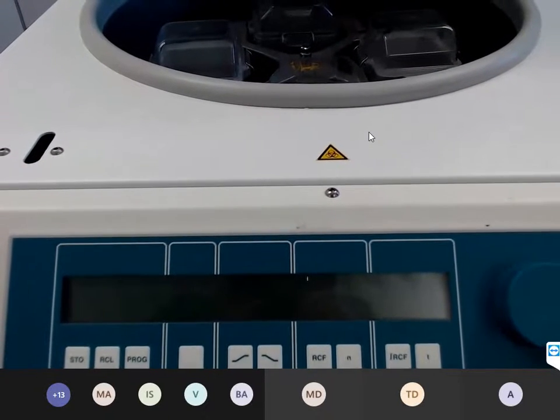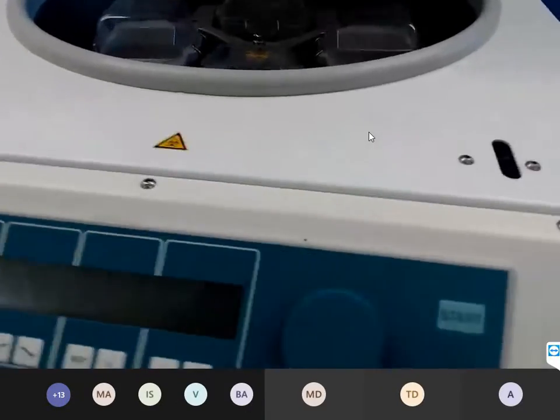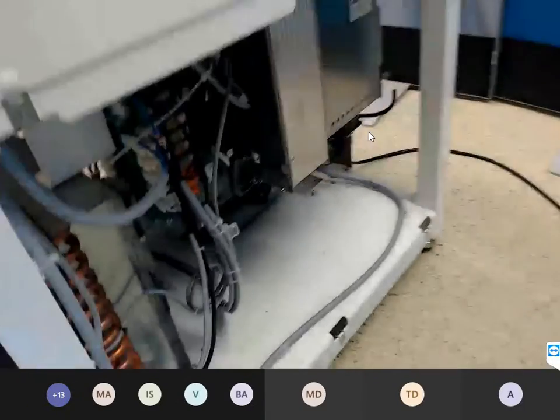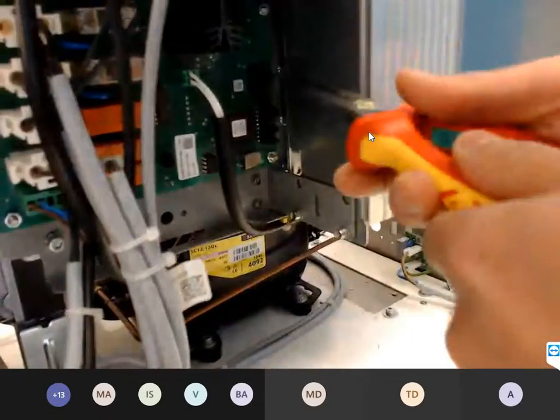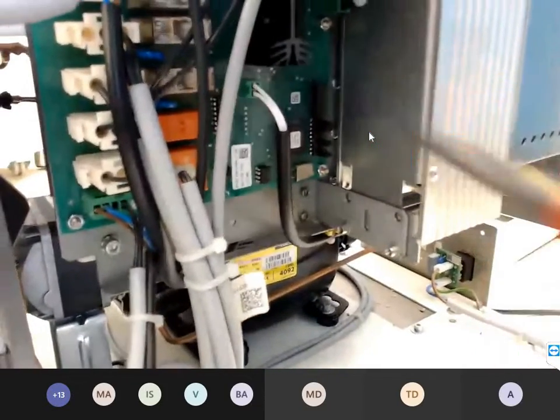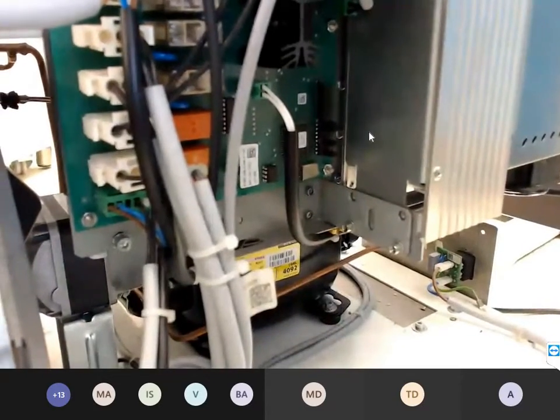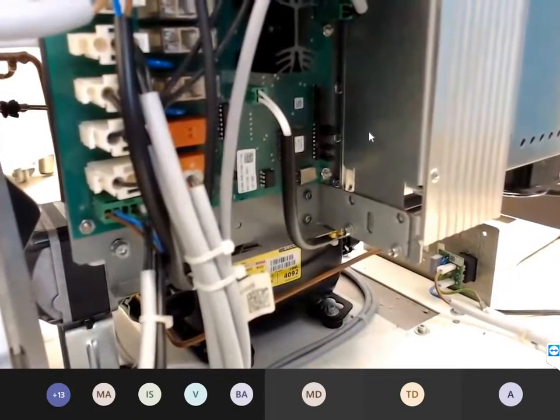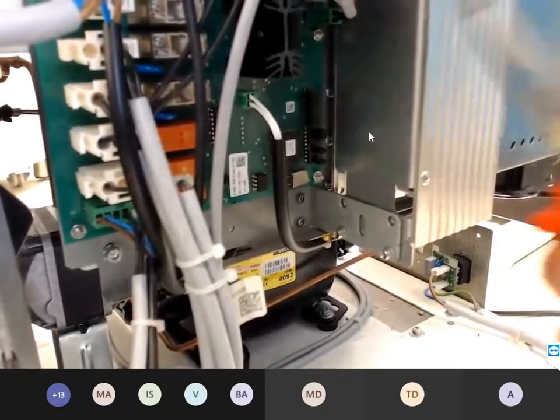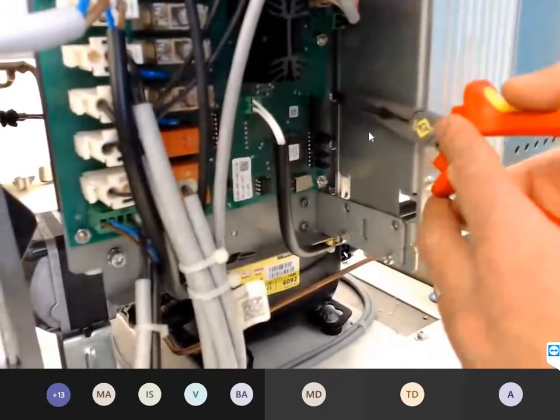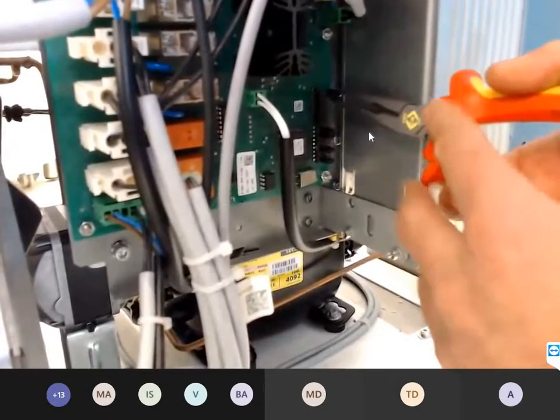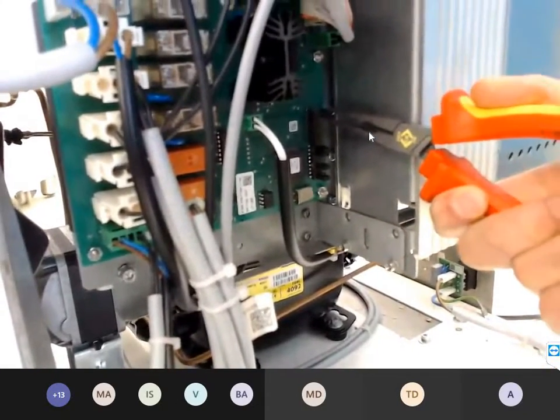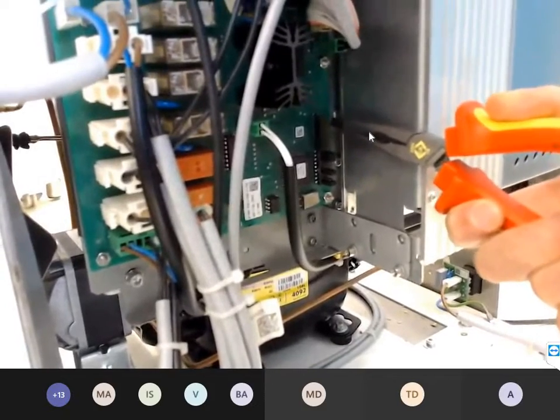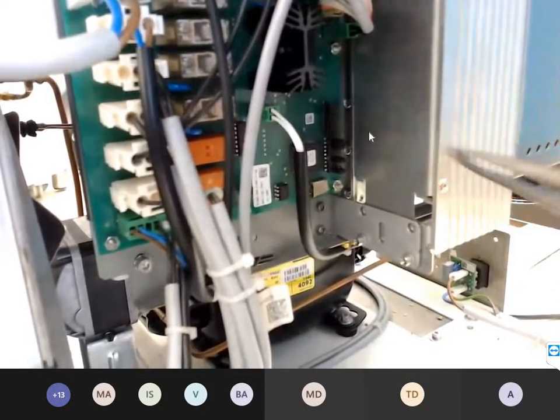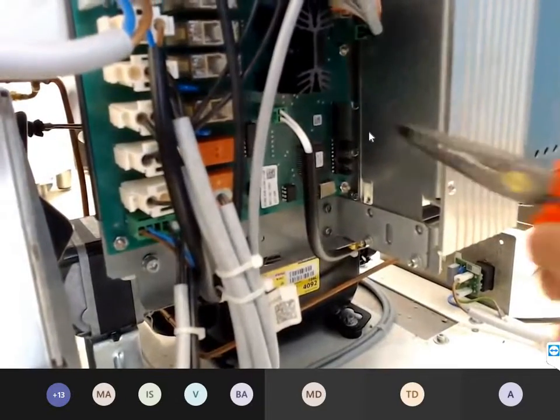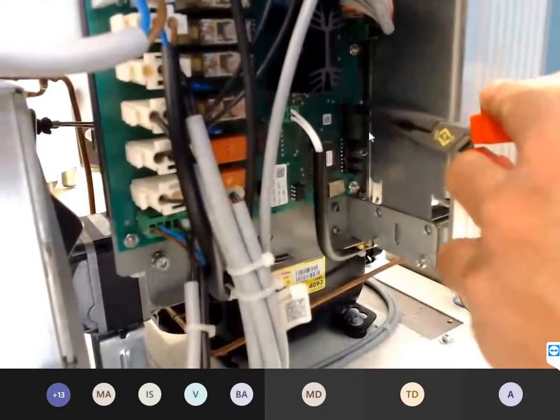So, switch off and change the jumper position in the normal position. I repeat, if you replace the control board, the frequency converter, or the electronics, we have to do initialization. And if you replace one of the temperature sensors, you have to make an offset setting.